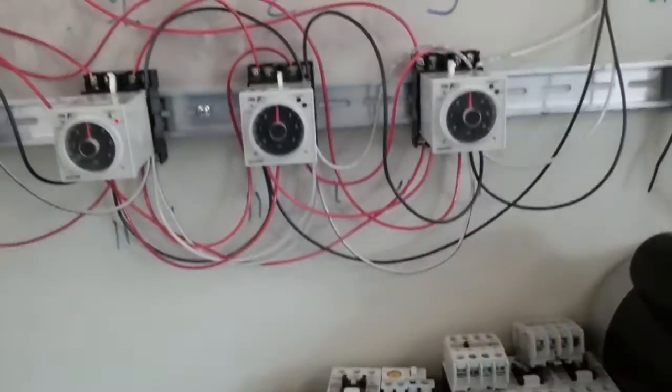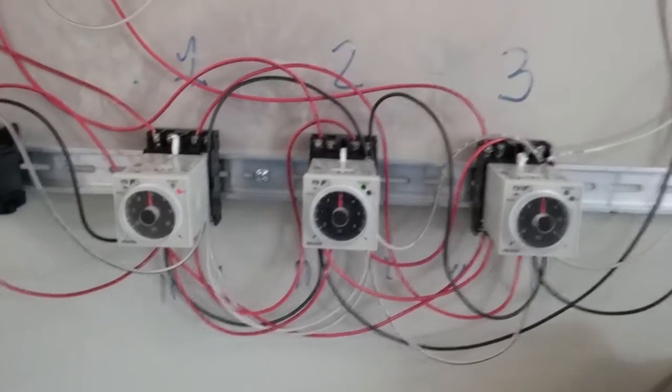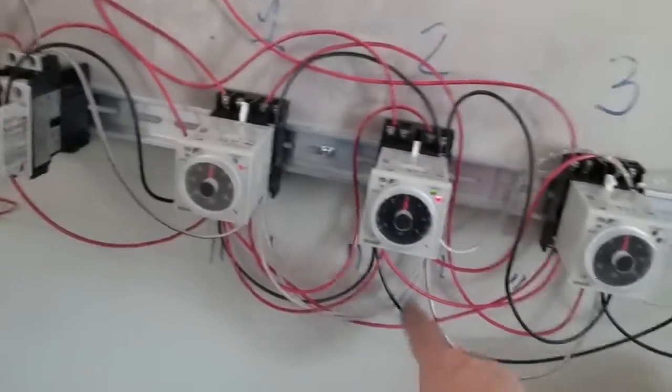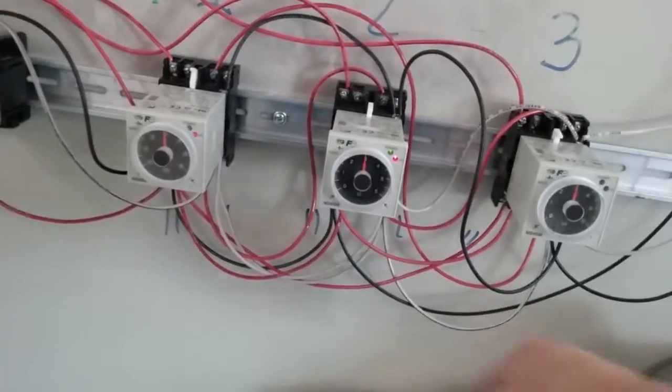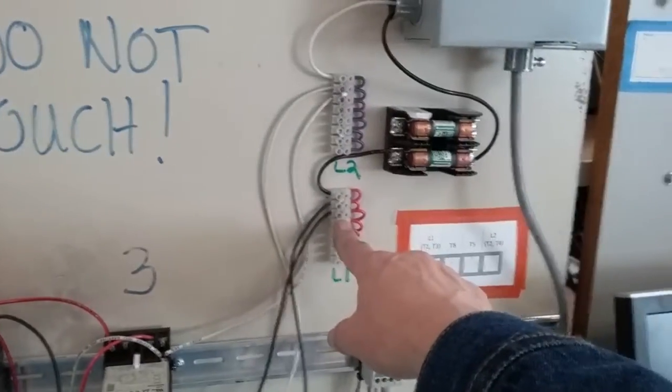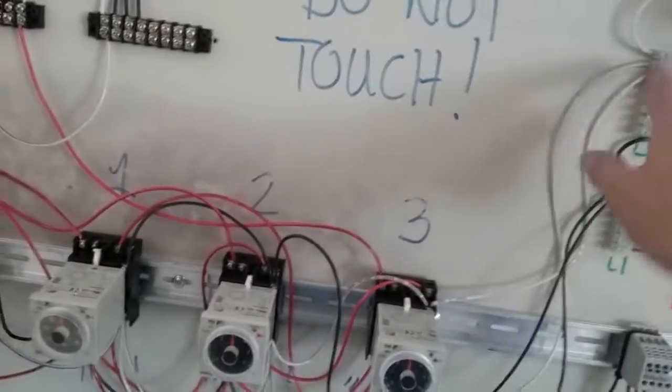You'll notice that when we turn on the power here up in the corner, the timers themselves do energize at that point. That's because we have the timers tied directly to the hotline. You see the black wires are all connected up here to L1 or hot. Our white wires are all connected to L2, which is our neutral, and the red wires are all interconnecting between them.